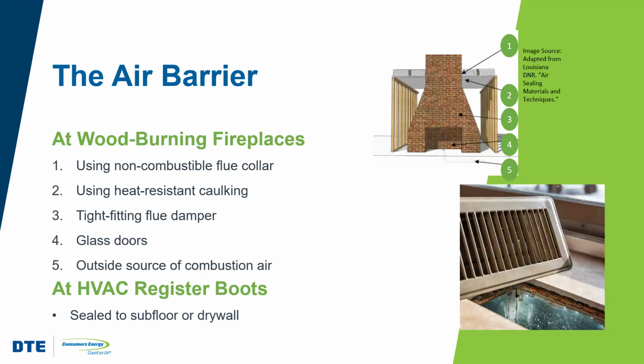Similar to recessed lighting housings, a good design will ensure that the HVAC register boots, whether they're for supply or return, are sealed. If they're in the wall, they're sealed to the drywall. If they're in the floor, they're sealed to that subfloor.